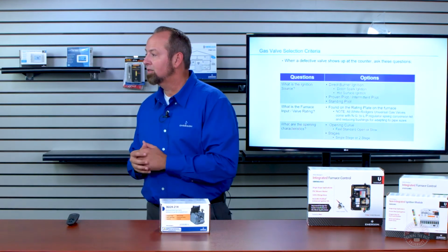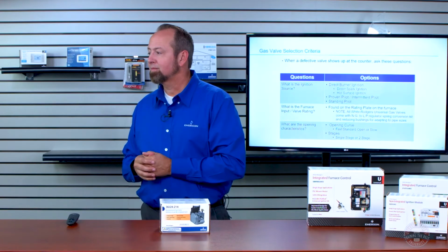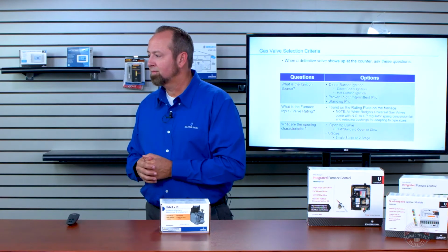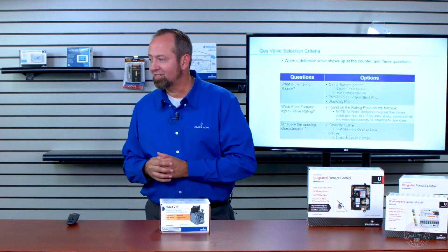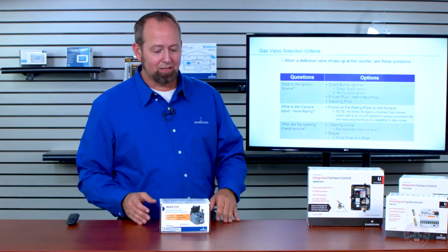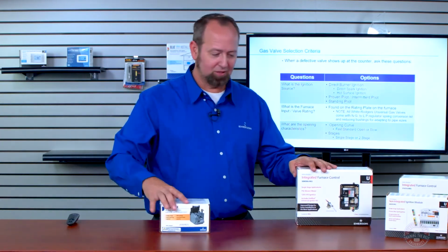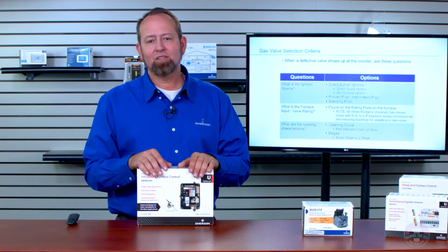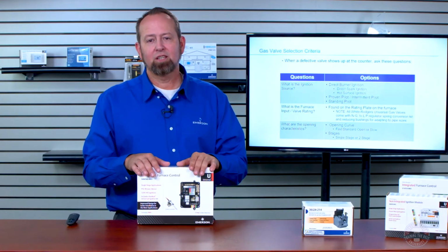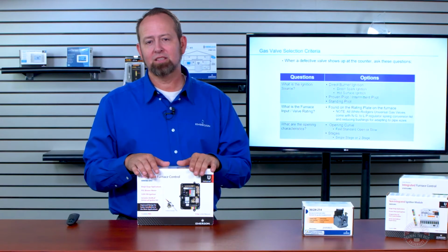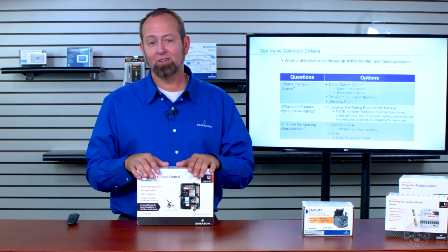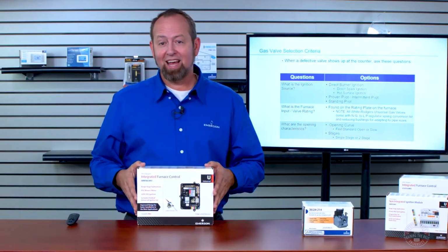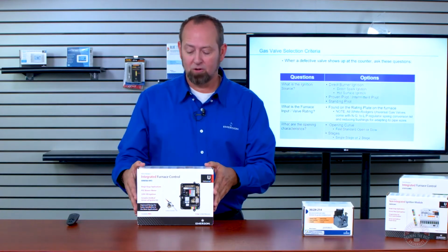We have a question from Kevin. The question is, on the IFCs, how elaborate are the diagnostic codes versus what the OEM boards would have? Great question, Kevin. The diagnostic boards on all of our IFCs, and we'll switch back to that real quick. I didn't touch on those, but on all of our universal integrated furnace controls, the diagnostics are either equal, greater, or much greater than the OEM. There are OEM boards that have no diagnostic features at all.